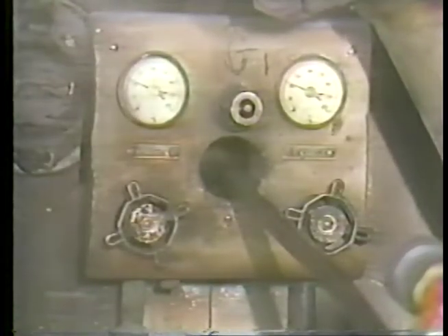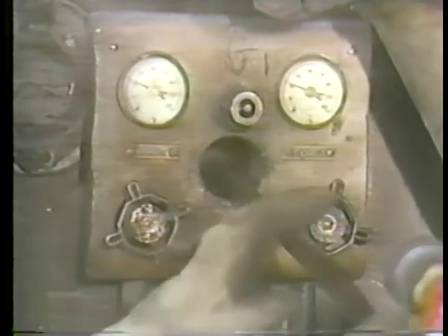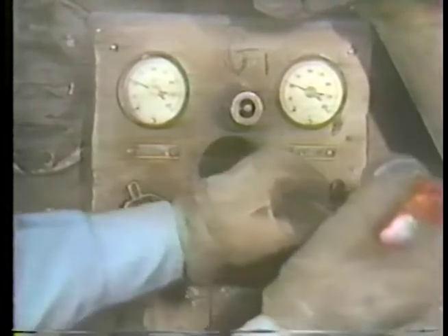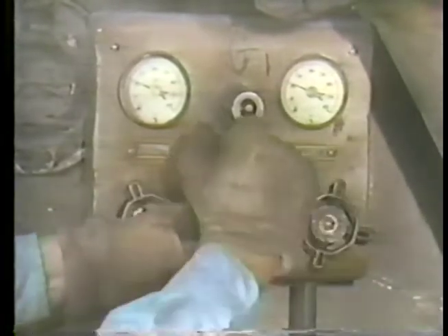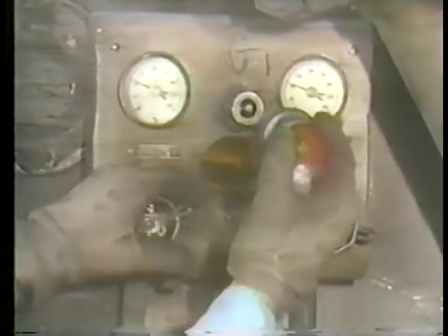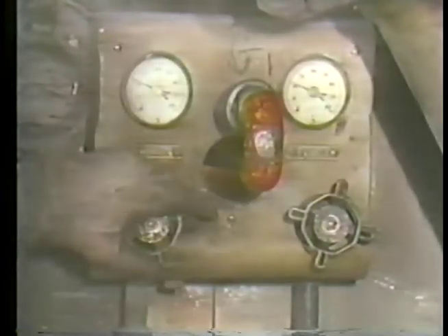This boiler uses removable oil burners for warm-up. When the igniter flames are stable, the operator inserts a warm-up burner into the burner port. He pushes the burner through the port several times to clear away any ash or slag that may have accumulated in its opening. He then connects the burner to the port and opens the valve on the line supplying atomizing air to the burner.